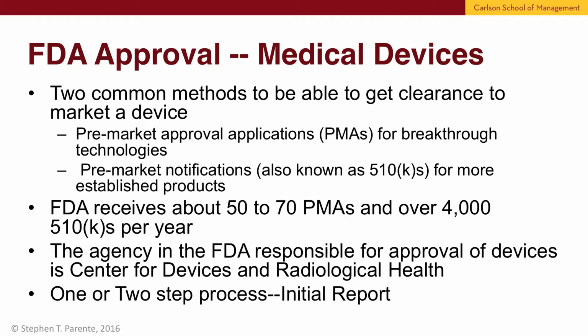So we talked about getting FDA approval for pharmaceuticals in the previous module. Let's talk now about getting approval for medical devices. It's a different process, and there are two common methods by which to do this. The first is what's known as a PMA, for pre-market approval for breakthrough technologies. These are really extraordinary technologies, things like those implantable cardiac defibrillators we've talked about before, essentially the CPR machine in your chest.